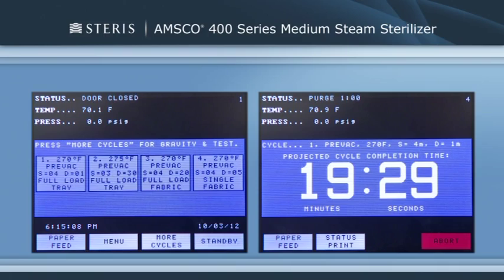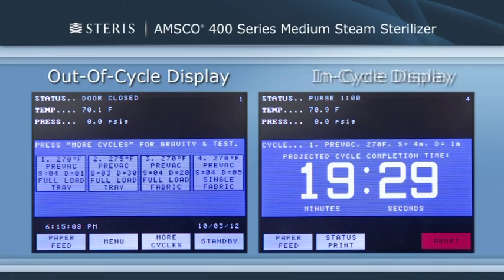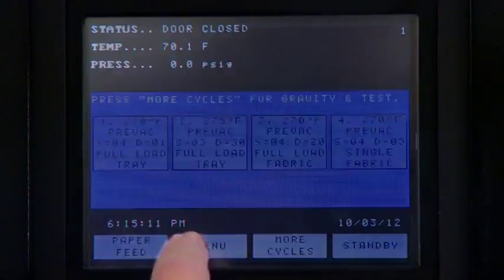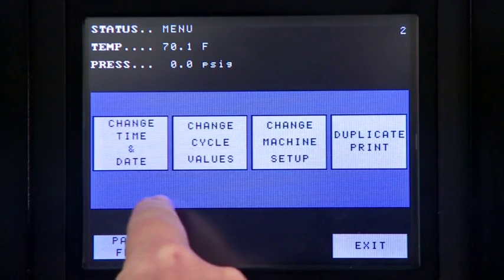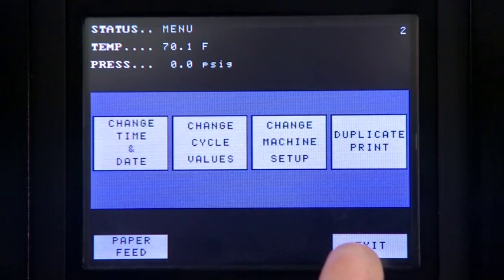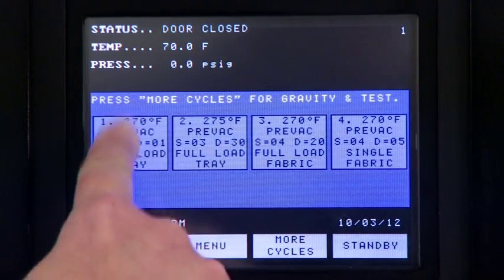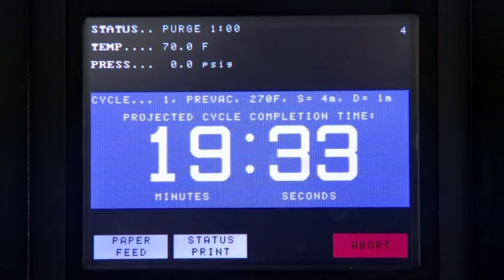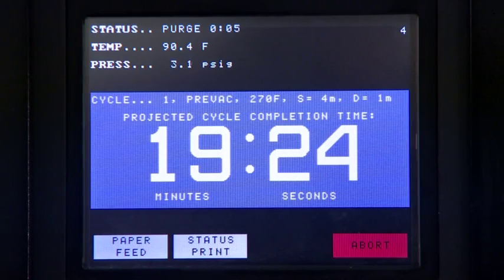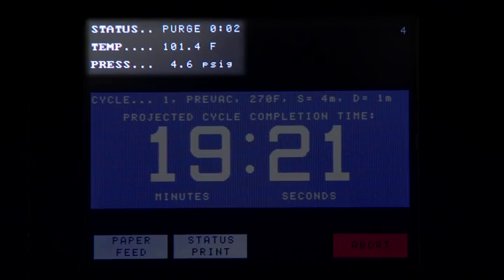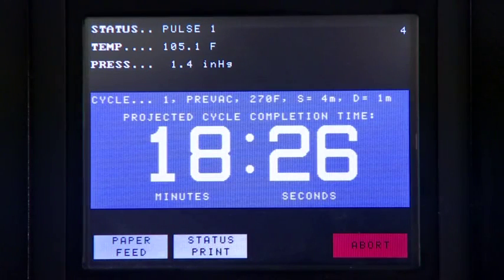Now, let's cover the control displays, which can be divided into two categories: those occurring when the sterilizer is out of cycle and those occurring when it is in cycle. Out-of-cycle displays are used to start cycles or set up and adjust sterilizer operation. With the exception of the cycle starting displays, most out-of-cycle displays will only be used occasionally. When the sterilizer is in cycle, displays generally appear automatically, and unless an abnormal condition occurs, require no special attention or instructions. In-cycle displays tell the operator at what temperature and pressure the sterilizer chamber is operating, show the current cycle phase, and indicate when the cycle is complete.